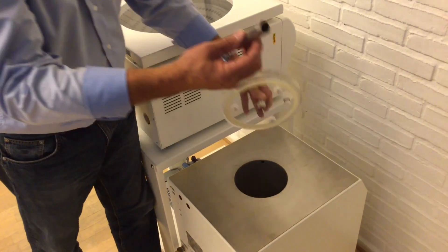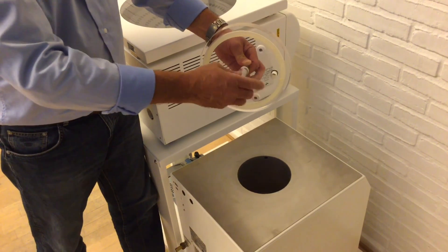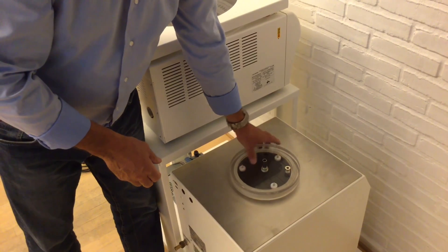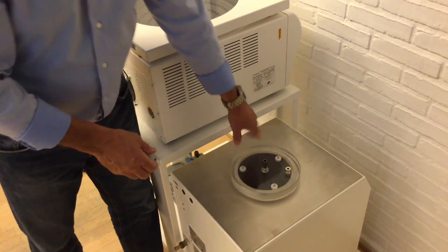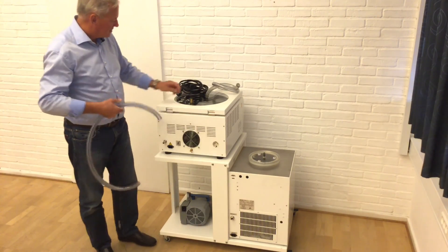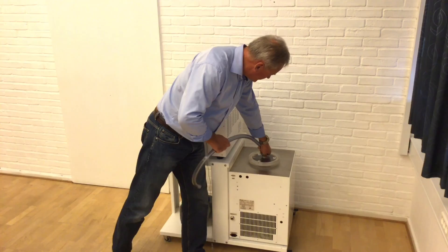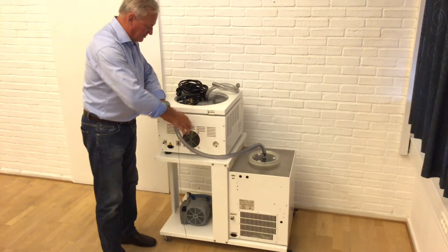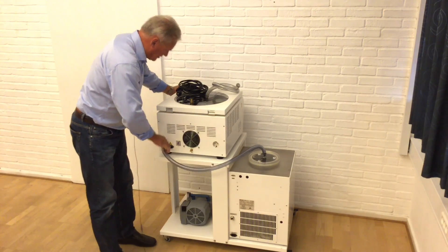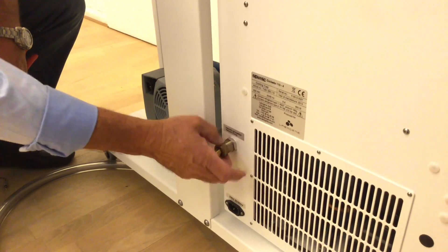The CTPL lid has an extra pipe which you can connect easily on the side, which will ensure that the vacuum flow or vapor flow will go better into the Cool Safe. You will start to connect the hose — you have a clamp. From the Cool Safe you will connect it directly to the Scan Speed 40, and then connect the hose connector at the Cool Safe.